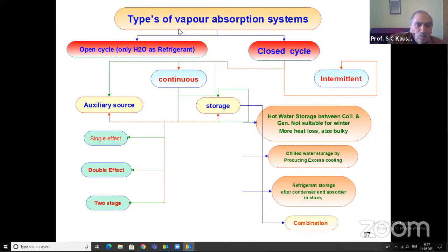Now, these systems can also be operated in the open cycle mode. Open cycle systems we will discuss next, but here I would like to mention that for the continuous operation of closed cycle systems, single effect, double effect, two-stage, triple effect, or multi-stage systems can be there. So continuous 24 hours operation with the help of solar energy is possible with the single effect, double effect, or triple effect cycles. And we may have to provide, you can see, these storage options or auxiliary heat source.